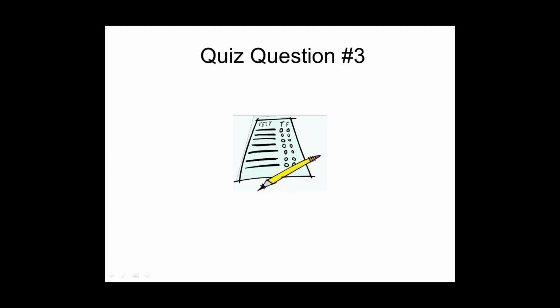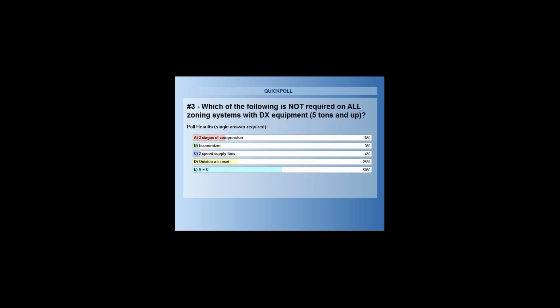All right, so I'm closing this question in 5, 4, 3, 2, 1. And I can tell based on the answers and how long it took people, and the fact that only 86% answered, that I must have written the question in a way that was hard. So you can see on the screen there. The question is, which of the following is not required on all zoning systems 5 tons and up? So 3 stages of compression is required on all zoning systems. Economizer for that size system is required. 2-speed fans is required. Outside air reset is not required. So the correct answer is D, outside air reset. Most people did not get that correct, so I think maybe I got everyone confused with the not and the all words. That's the only thing I could think of there.